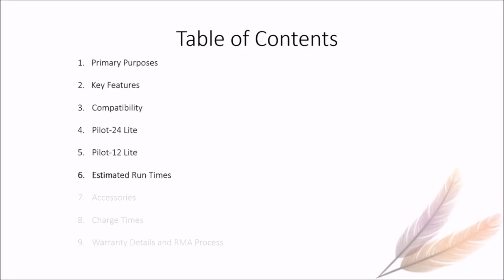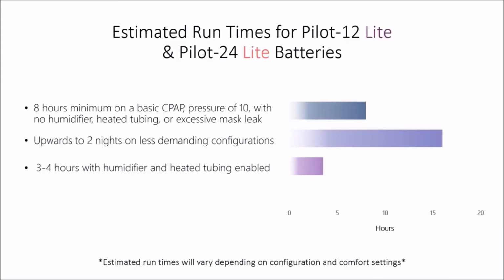We will now review the runtime for the Pilot 12 and Pilot 24 Lite batteries. The estimated runtime for the battery is between 8 to 16 hours. This is at a pressure setting of about 10 centimeters with the heated tubing and humidifier turned off. At less demanding settings with a lower pressure, you can expect a runtime closer to the 16-hour mark. If you were to use the battery with the heated tubing and humidifier enabled, this would significantly decrease the runtime to approximately 3 to 4 hours. It is important to note that a poor mask seal can also contribute to a severe drop in the runtime.